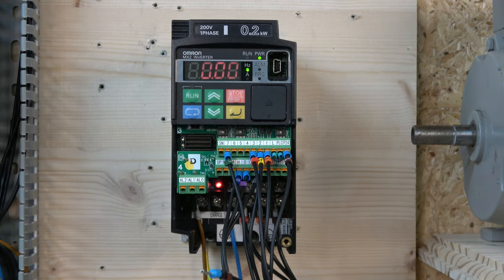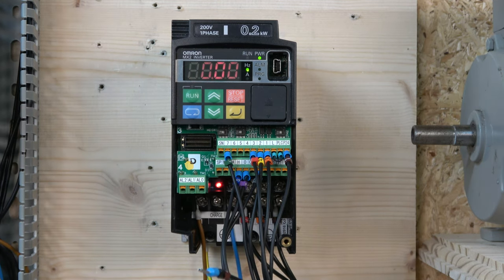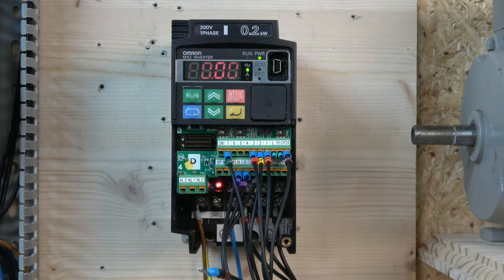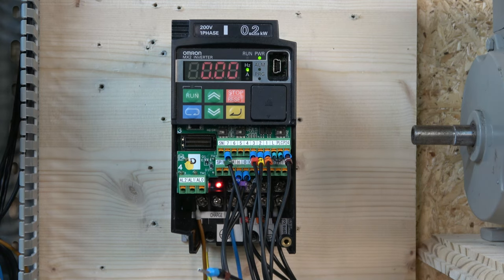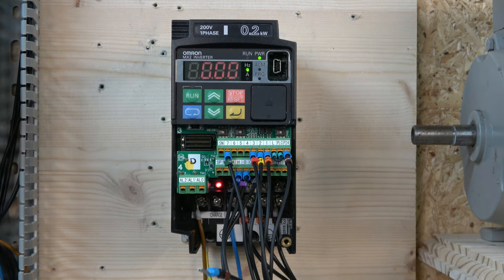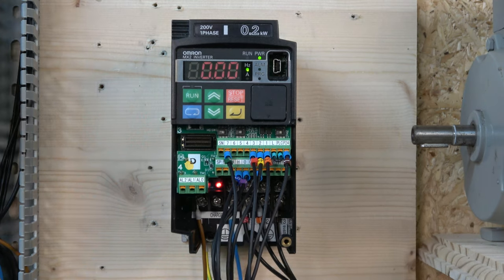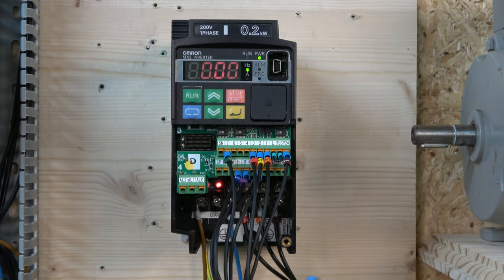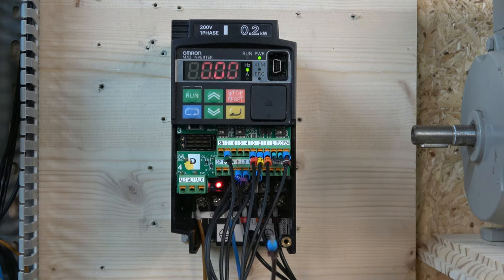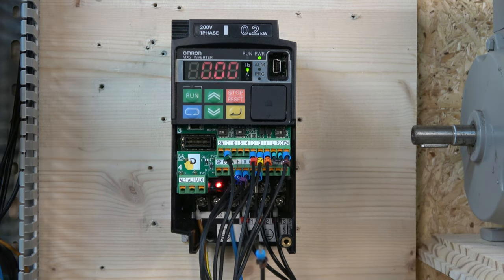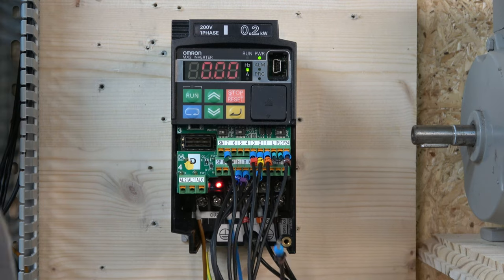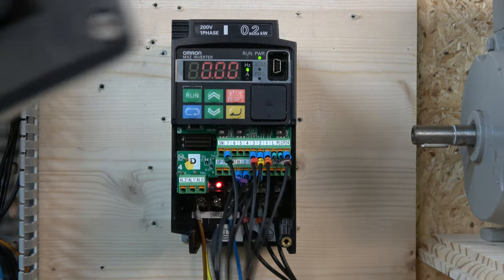Let's just get back to V. Regarding setting up your jog, what sort of parameters you need to use to adjust it. If you want to change the jog frequency, it's 838 and 839. We can check out 839 now. There's a bit more to it, but 838 if you want to change your jog frequency. And one more thing you have to remember is make sure that your A1 frequency source is on 01 and A2 your run command is on 01 as well, so both on 01.